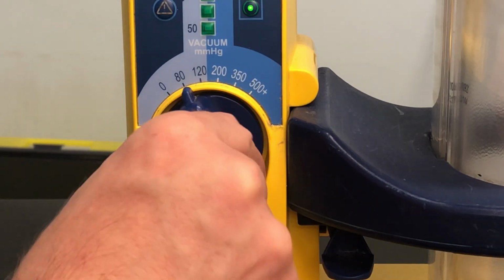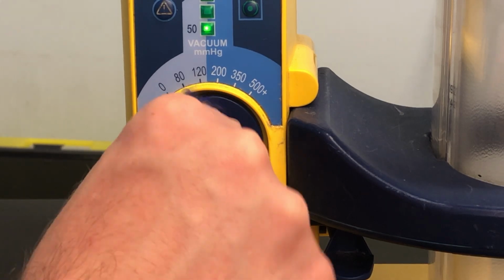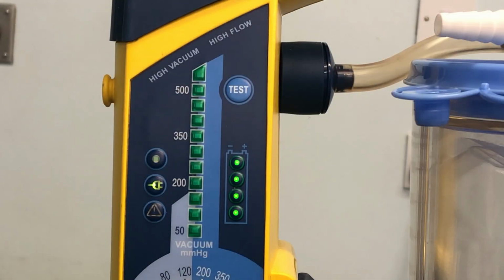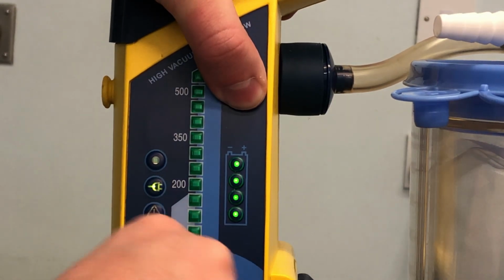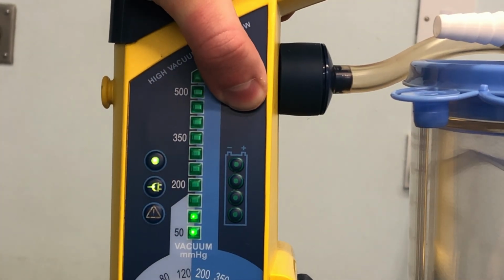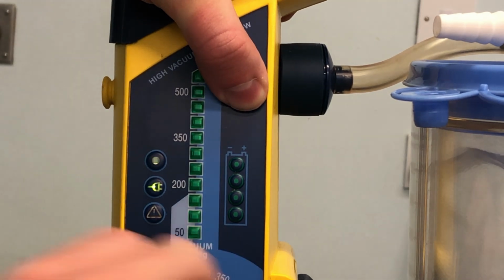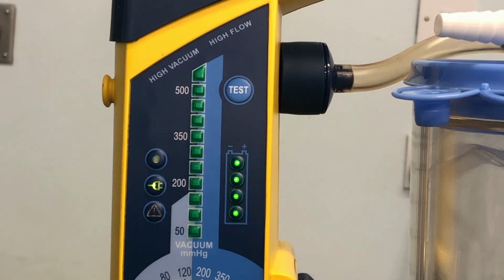Moving on, we have the operating knob. This is a combined on-off switch with vacuum select. There is a test button, and this button allows you to run a 4-step user-initiated device test program to identify whether the LSU operates satisfactorily, it is assembled correctly, or if it needs service.